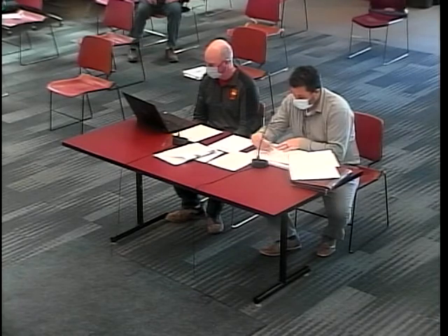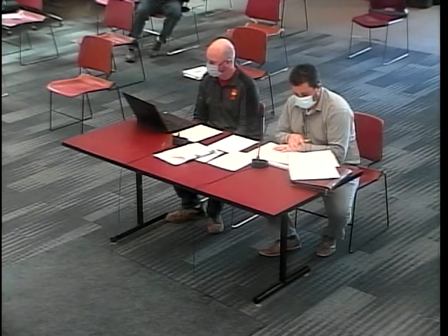So you're kind of pigeonholed there. The district has had issues with the unit ventilators in the past, with them freezing up because they draw outside air, and then you get a leak in the classroom, and it's been a mess. So the district's request was to centralize the HVAC into a few new units that they can maintain, and distribute it all with ductwork. With the time constraints of doing the work only in summer hours, and also the cost, running the ductwork on the roof made the most sense, as opposed to tearing apart all the ceilings, building new soffits inside the school, and relocating a bunch of electrical, when you have wide open space up on the roof already. That was the design intent behind what brought us to this on Valley View.